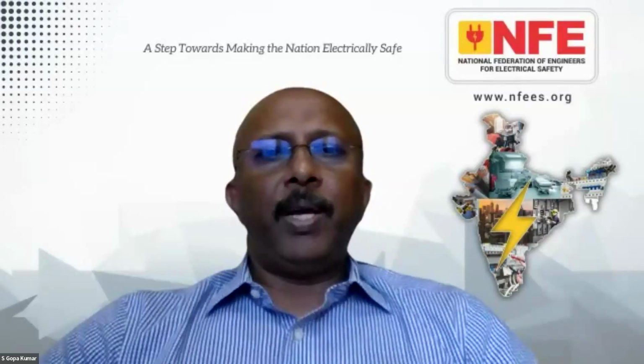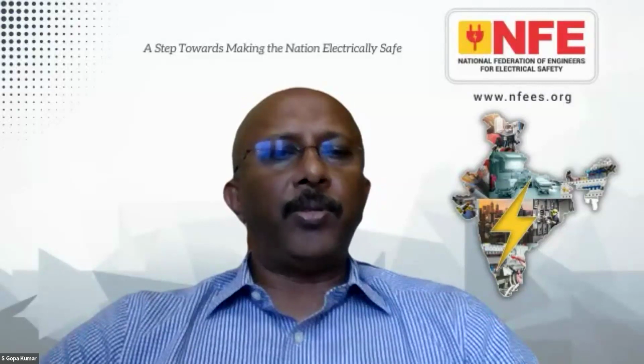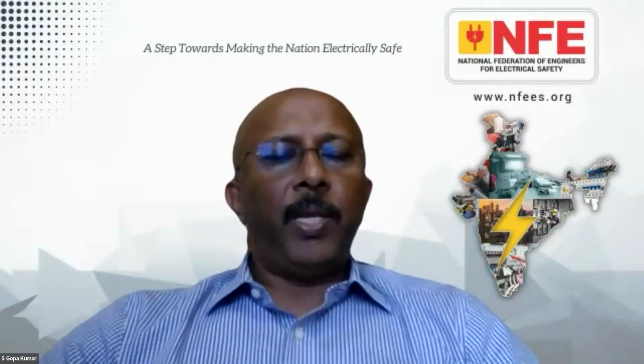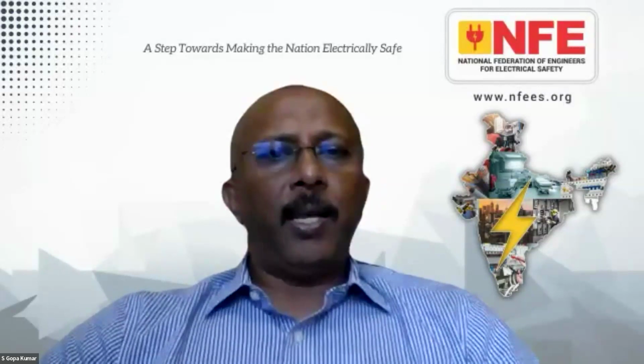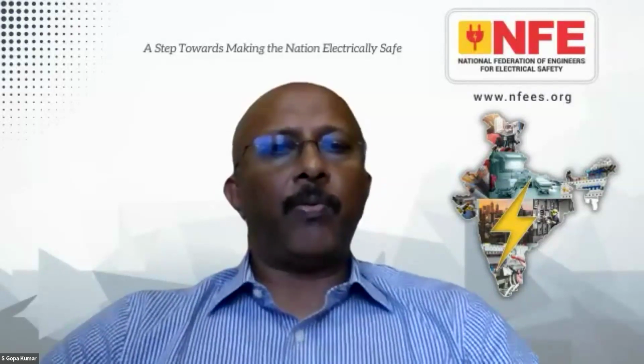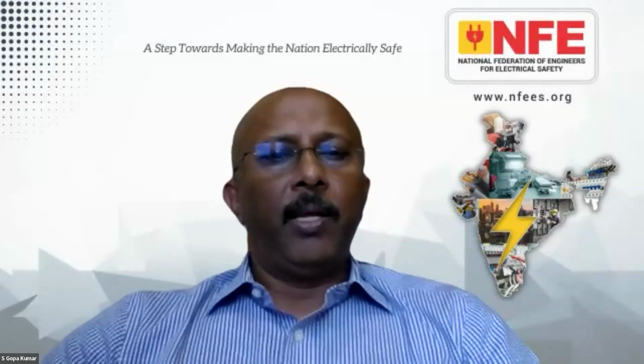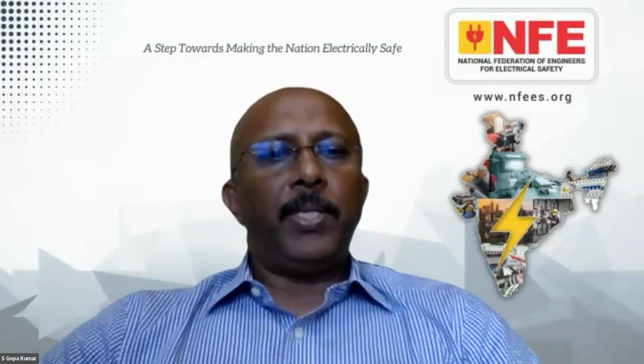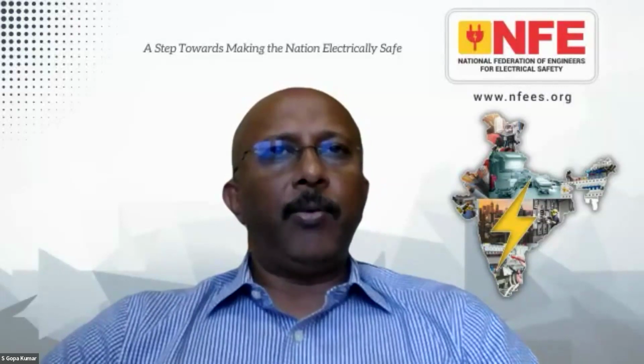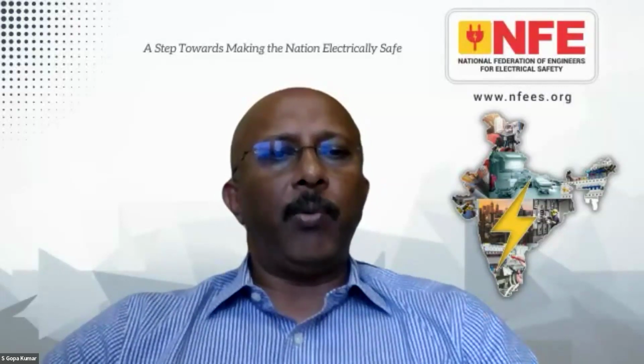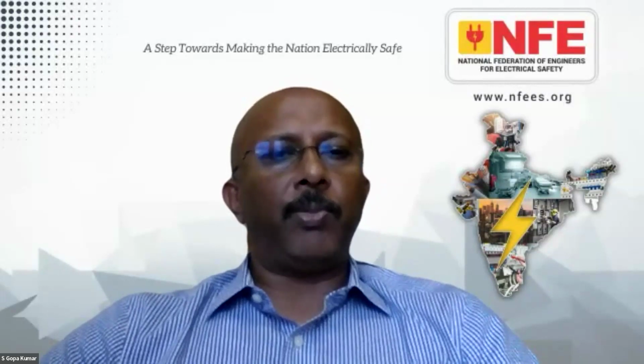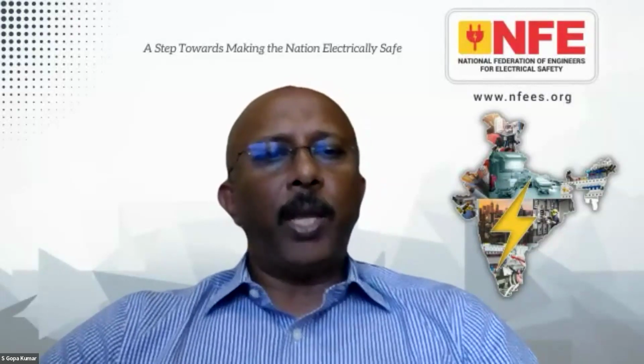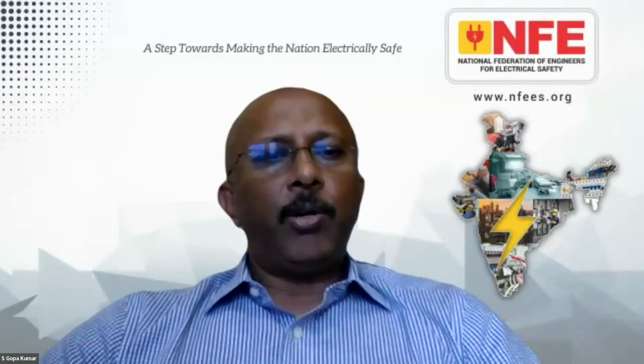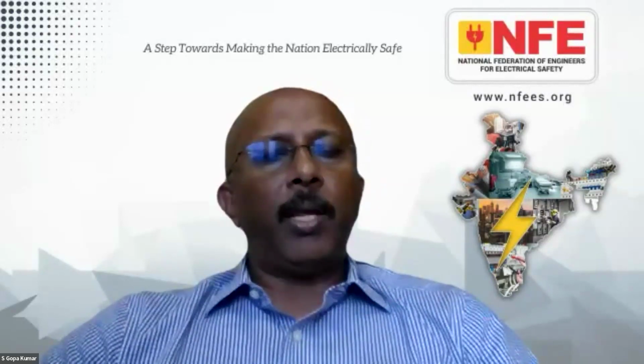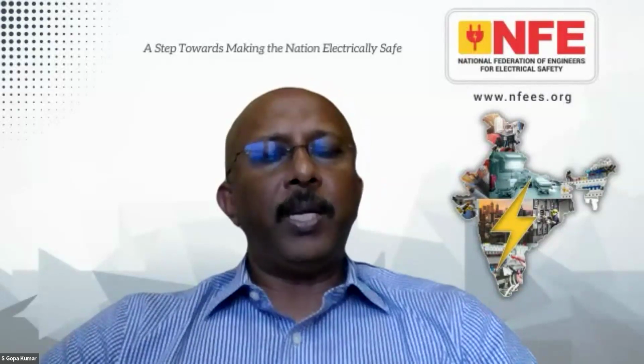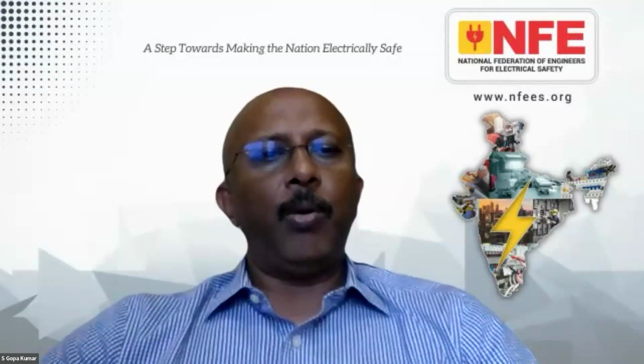Sir, actually, this device is not injecting any additional voltage into the system. First of all, it is there in IS 732. If you look at clause 1 of the annexure, it is very clearly explained. It measures the operating voltage, let's say line to neutral or line to earth, 230 volt. First, 230 volt is measured. Next, for 2 cycles, it makes a short circuit of the line and earth or line and neutral through a fixed resistor, let's say a 10 ohm resistor.